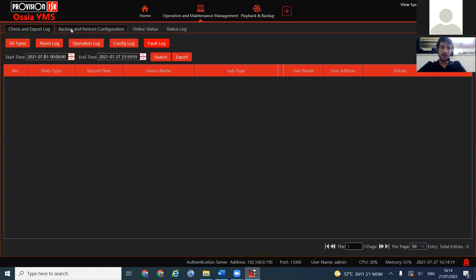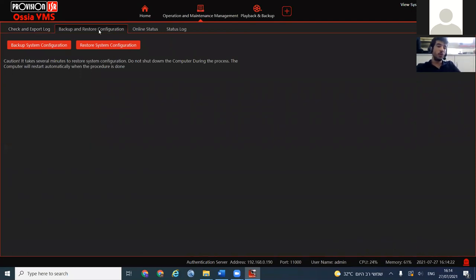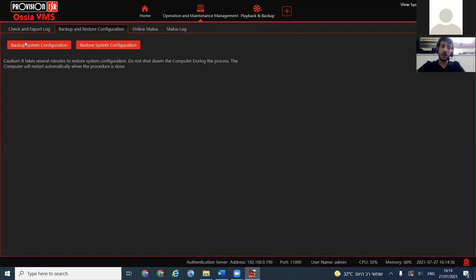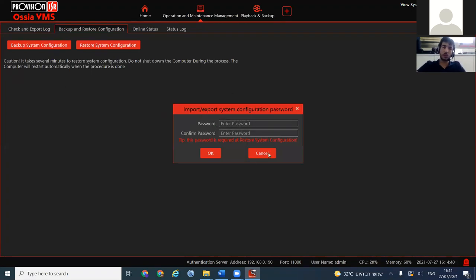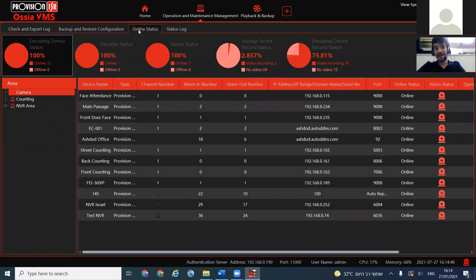Our next section is Backup and Restore Configuration. We get this question many times: how can we back up our system? If you've created many different users, permission groups, alarm linkages, and saved views, you can back up the system configuration here. You provide the system password to do that, and then you can restore it on a different or the same computer — a way to keep your settings alive at all times.